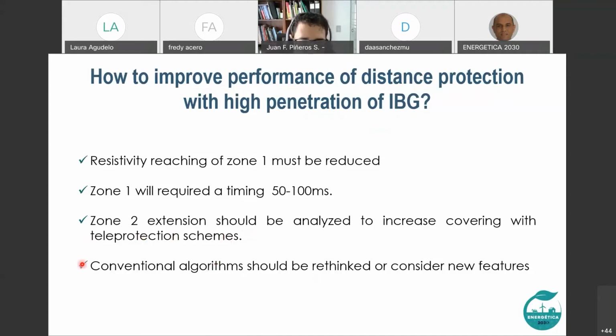And a last point: conventional algorithms should be rethought, or new features about distance protection should be considered. Why? Because as we are now checking, the behaviors of the impedance trajectories are not the same, so in a way we cannot use the same algorithms if we want to have a better performance.